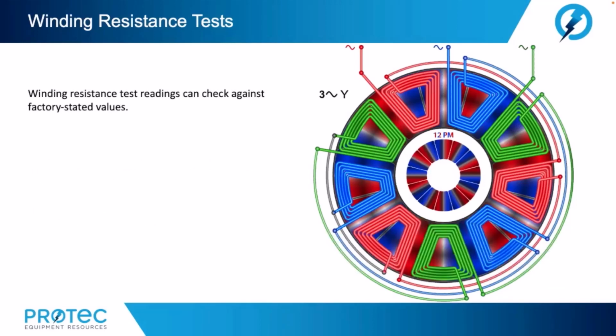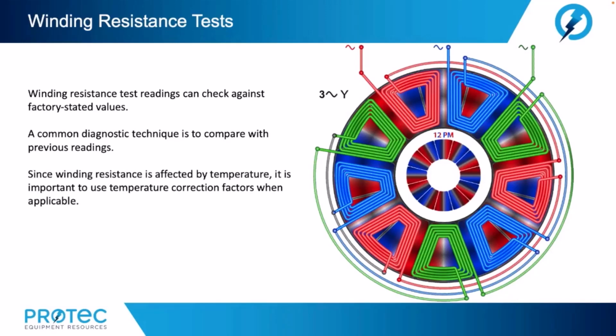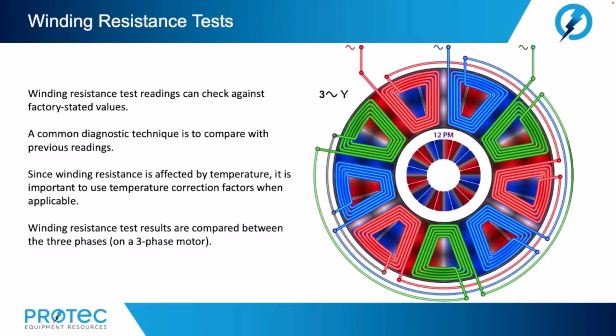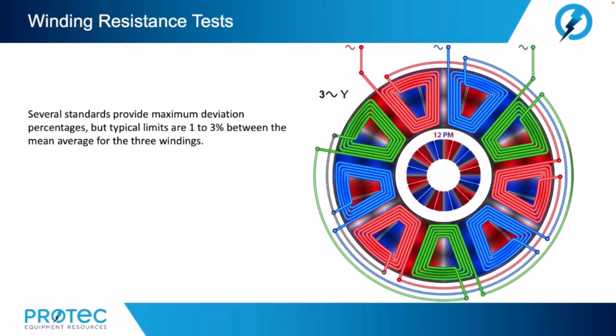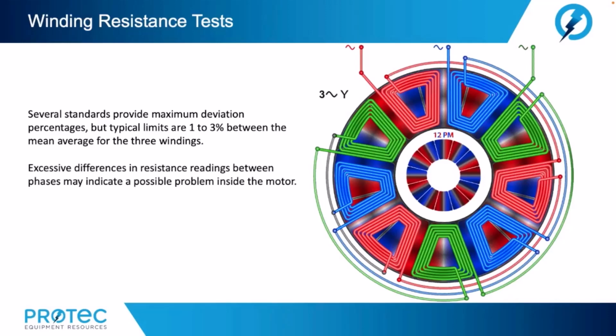Winding resistance test readings can be checked against factory stated values. Now, a common diagnostic technique is to compare with previous readings. Since winding resistance is affected by temperature, it is important to use temperature correction factors when applicable. Winding resistance tests are compared between the three phases on a three-phase motor. Several standards provide maximum deviation percentages, but typical limits are 1 to 3% between the mean average for the three windings. Excessive differences in resistance readings between phases may indicate a possible problem inside the motor. Winding resistance is also used for measuring I²R or heat losses in the windings.